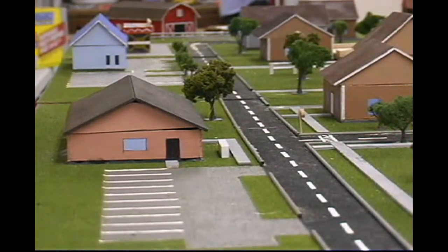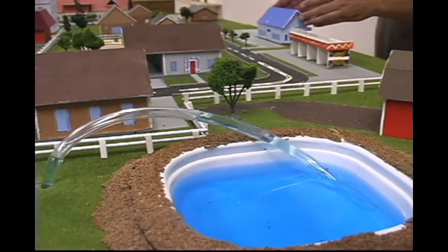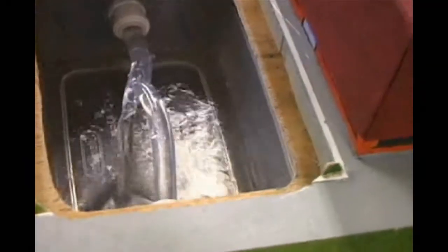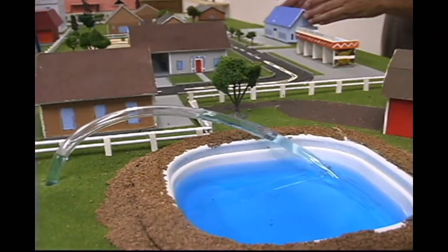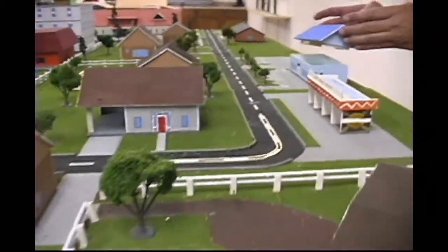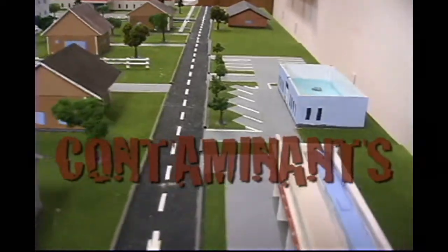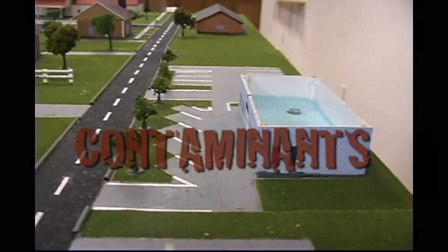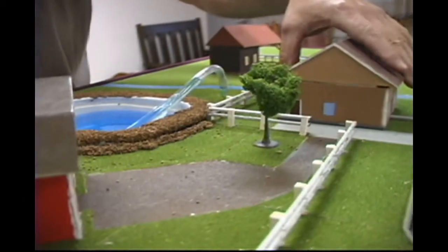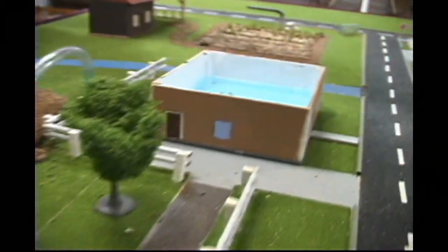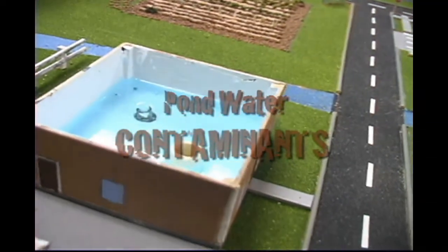And down the road in the rural farm area, remember the hose that was left laying in the pond? When the main line broke, pond water backflowed into the main water supply line. Once the repair was made and the line repressurized, contaminants were dispersed throughout the water system, as evidenced by the blue tint in the water at the grocery store and the nearby homes.